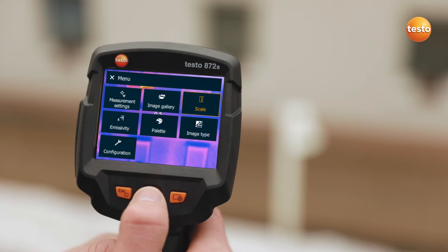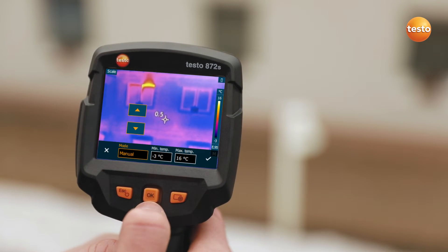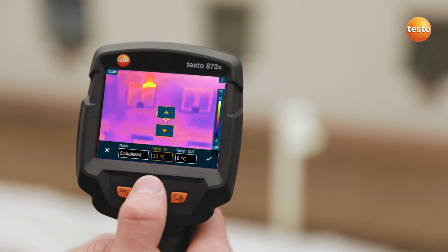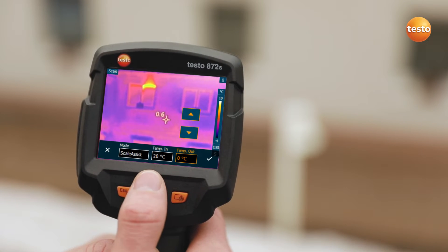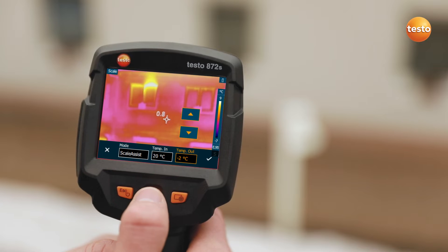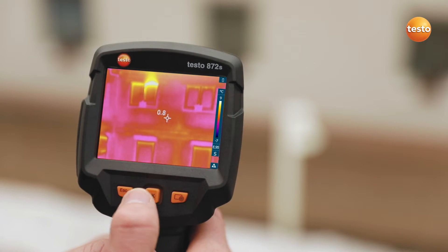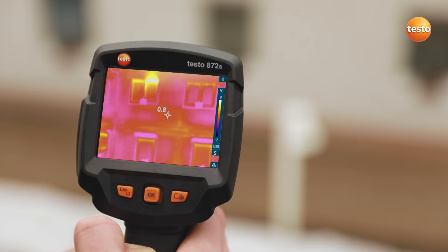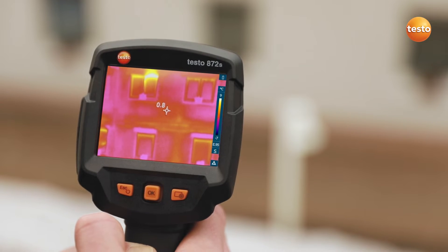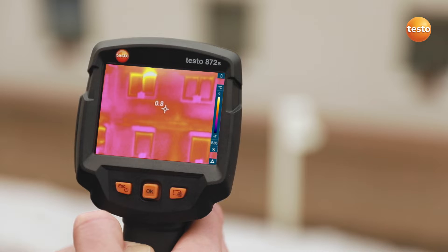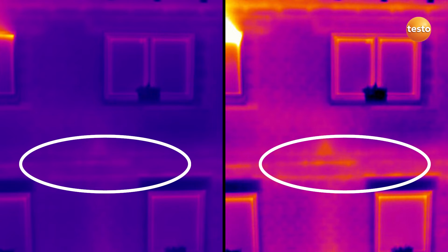You can set the scale of the thermal image automatically, manually, or with the Testo Scale Assist function. The Testo Scale Assist makes it easier for you to inspect facades and walls, indoor and out. The function automatically filters undesired temperature extremes out of the thermal image, meaning you see only the building faults and cold bridges which are actually there. Here's the comparison: on the left without, and on the right with, Testo Scale Assist.